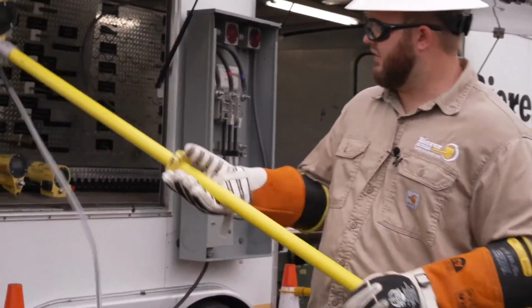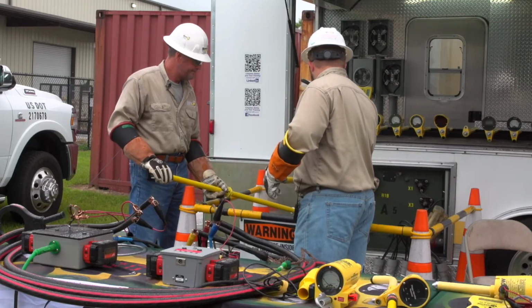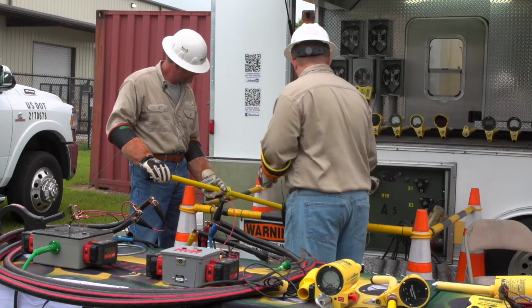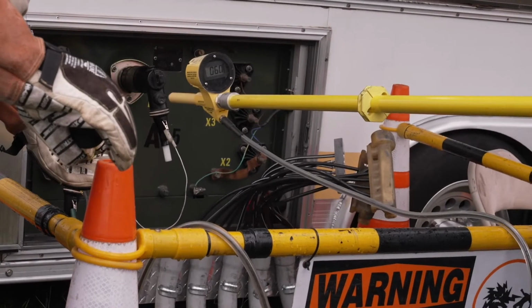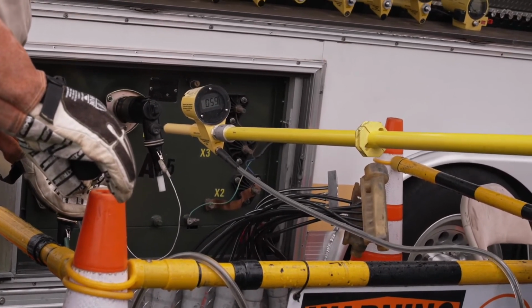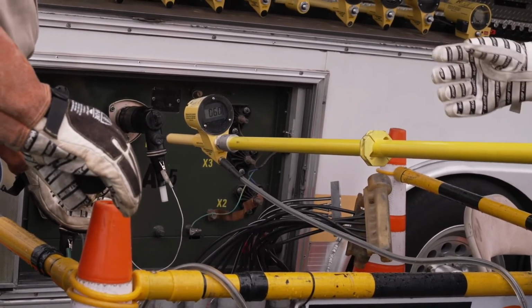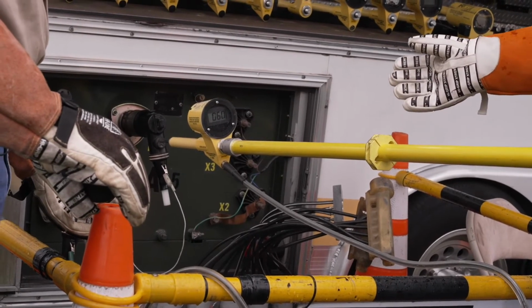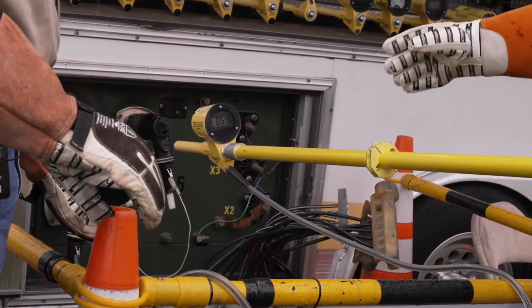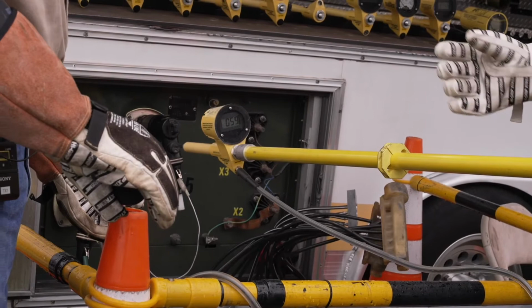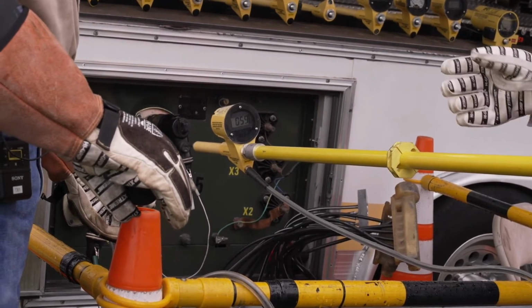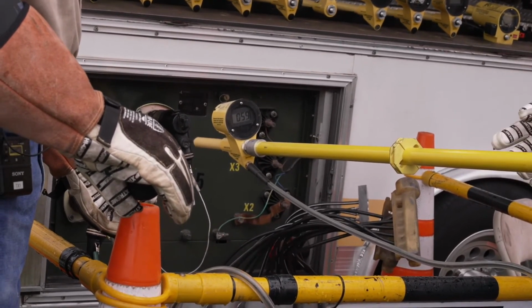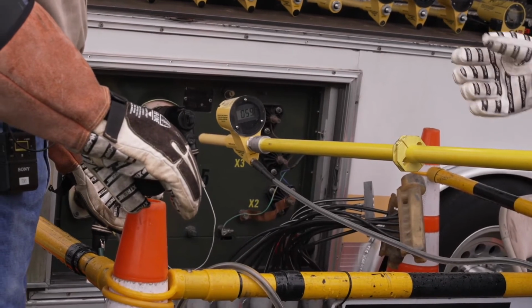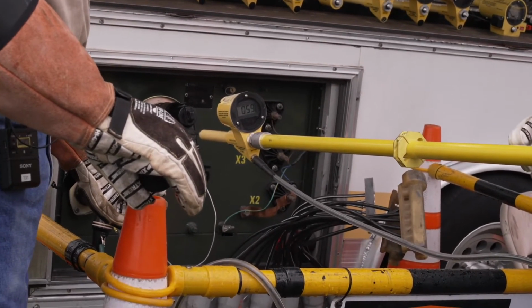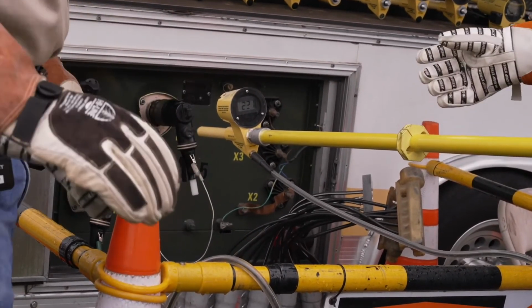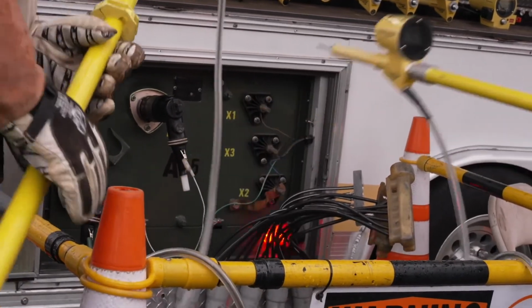So again, if we're in phase, we should see the difference of those two numbers, about 75, 80 volts. And we see a little bit lower, about 60 volts. But if we were out of phase, instead of a low number closer to zero, we would see that out of phase multiplier, about 1.72. So about 300 volts times 1.72, you'd see around 520 volts. So we know for sure that this is in phase.